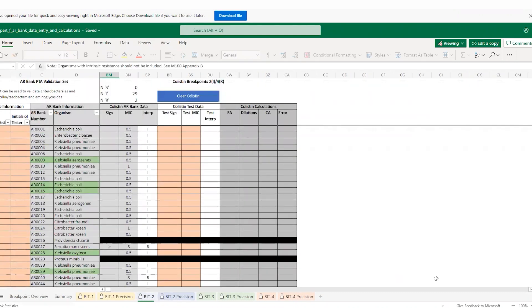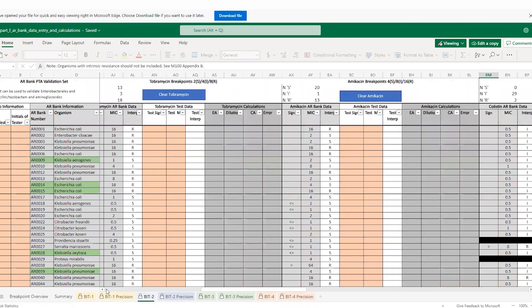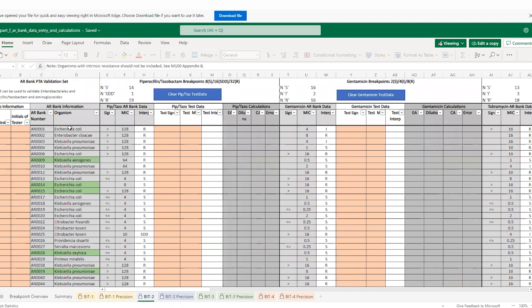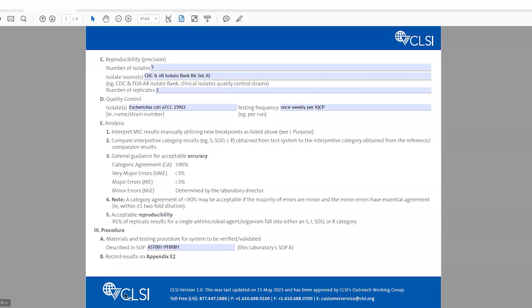You can go into the Excel spreadsheet and under piperacillin-tazobactam, you see the isolates from the BIT set outlined for BIT set 2. Any isolates highlighted in green are isolates that you can use for your reproducibility, and that was what was used for this particular validation. We also go over the number of replicates — in this case, we did them in triplicate. We describe what our quality control is, in this case E. coli ATCC 25922. The frequency of testing is once weekly per our IQCP. And all procedures appropriate for this validation study are outlined in our SOPs, both for our AST SOPs and our Phoenix SOPs.